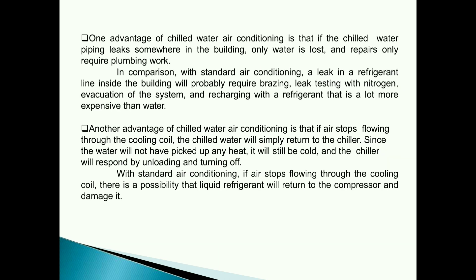One advantage of chilled water air conditioning is that if the chilled water piping leaks somewhere in the building, only water is lost, and repairs only require plumbing work. In comparison, with standard air conditioning, a leak in a refrigerant line inside the building will probably require brazing, leak testing with nitrogen, evacuation of the system, and recharging with a refrigerant that is a lot more expensive than water.